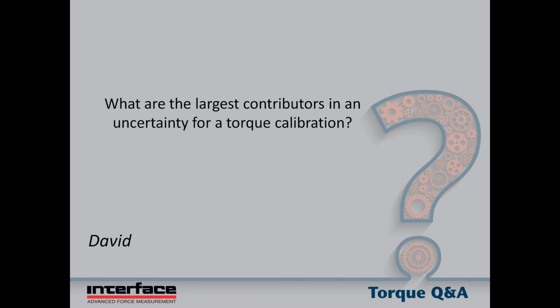What are the largest contributors in an uncertainty for a torque calibration? I think in many cases it's the actual application of the torque. And so if you're actually, say, calibrating a torque sensor, you can either do a comparison test where you're applying a torque to both sensors simultaneously and comparing the output of the device under test with the calibration standard torque sensor. In many cases with torque, the load is applied using dead weight on an arm.